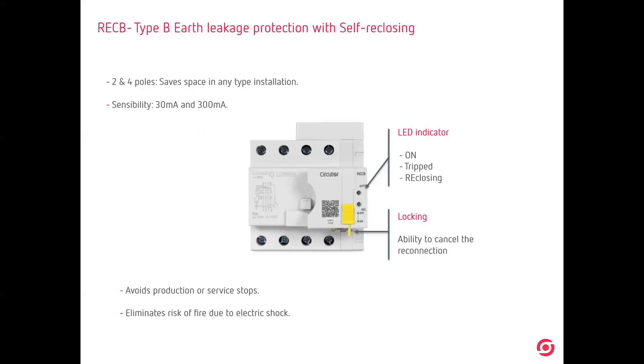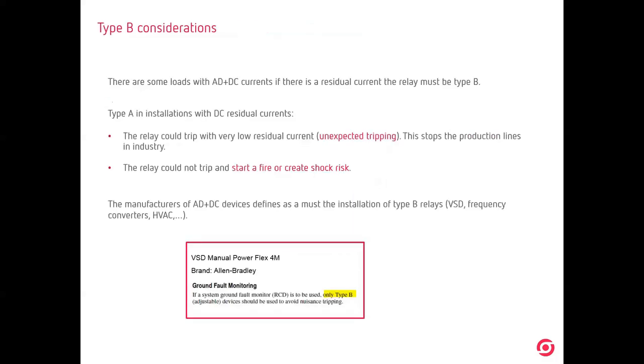So if you are using this self-reclosing system, you should connect it with type B loads, variable speed drives, all the loads, climate that we have seen. Type B considerations, very simple. If you install type A with DC residual currents, you can have 2 effects. The relay could trip with a very low residual current, so you can have unexpected trippings. This will create indirect costs because you are stopping the production. The OPEX will be increased. You are losing money, because type A is not designed to read DC current.